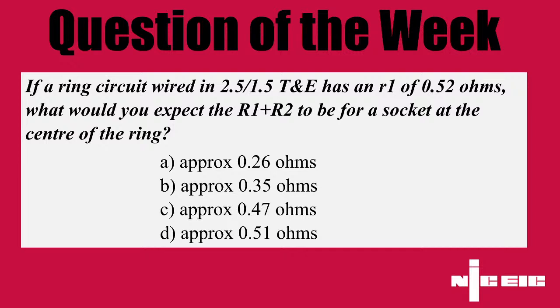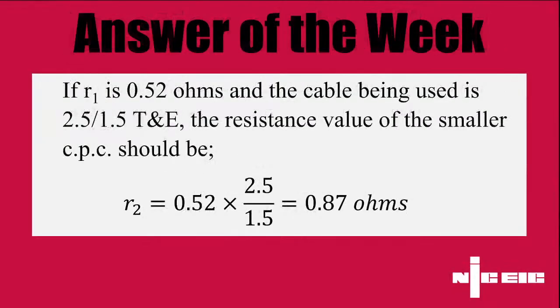So this particular question requires us to do a bit of maths, as Sam said. First of all, we need to understand that the cross-sectional area of copper conductors changes the resistance of that cable. And because the cross-sectional area of the 1.5 CPC is smaller, it means the resistance will be greater. But there is a correlation between the cross-sectional area and the resistance. So to work that out on a 2.5/1.5, you take 2.5, divide it by 1.5, and you get a value of 1.67.